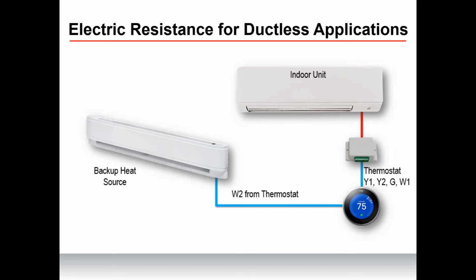You can also utilize the controls strategy as this slide represents. In this instance, you would use a thermostat interface plugged into the indoor unit. A third-party thermostat would then be wired from the electric resistance heat source to the thermostat interface. From the thermostat, W1 would control the heat pump as first stage, and W2 would control the backup heat source as second stage. Thermostat interface is proprietary.